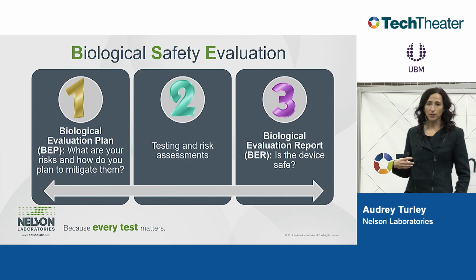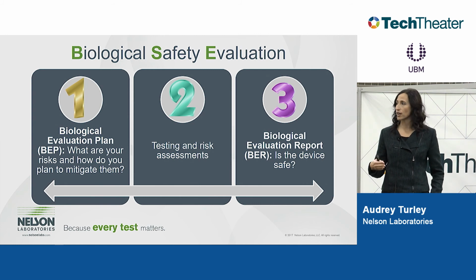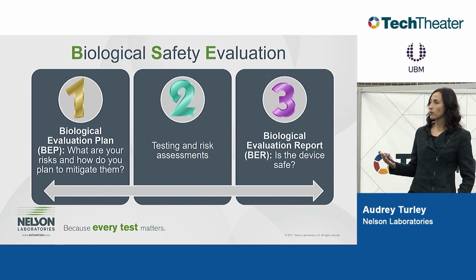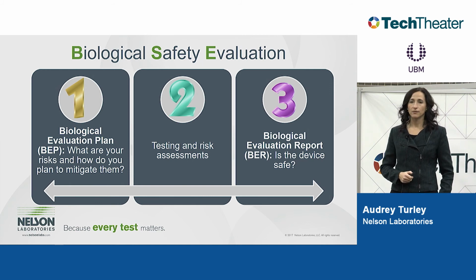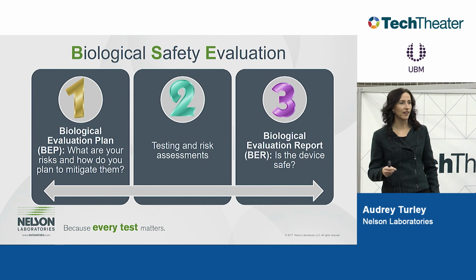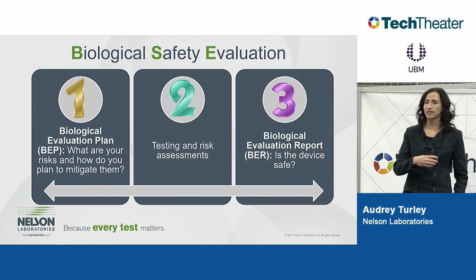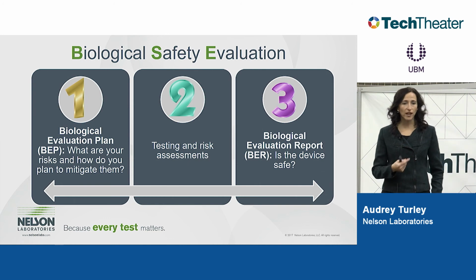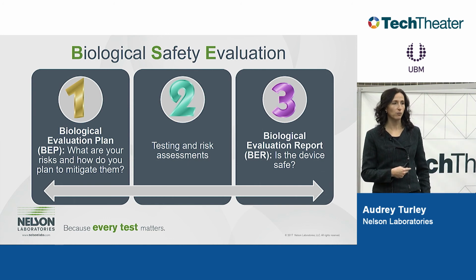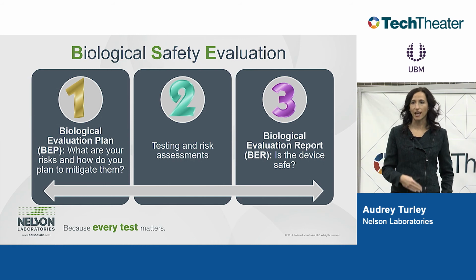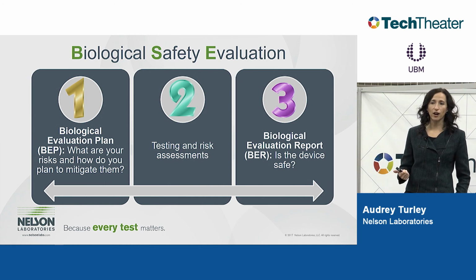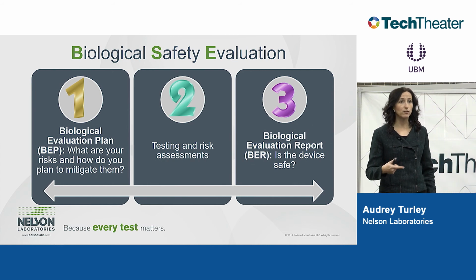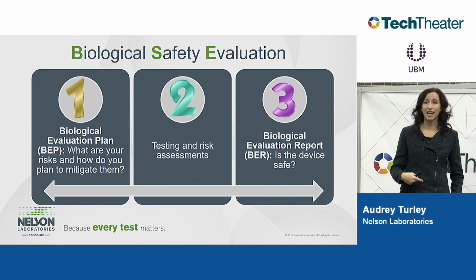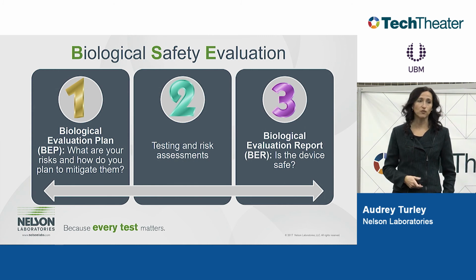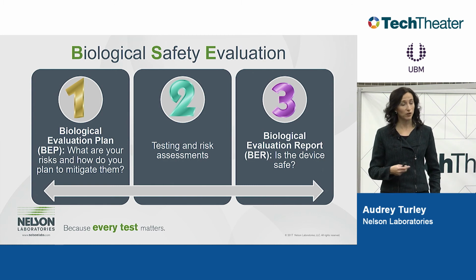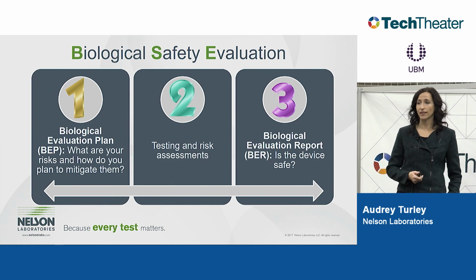So we step back out to this big picture. We've done step 1, we've done our testing, we've done our risk assessments, our chemistry testing, and now we're going to do a biological evaluation report. This sometimes gets a little bit of oversight, I think, and the engineer who was in charge of coordinating all the testing is just going to write everything up. But what we're finding is that agencies are coming back and saying we need somebody with the proper education and experience to say your device is safe. So they want somebody with some biocompatibility background, a toxicologist if necessary. Maybe you didn't do a separate toxicological risk assessment, but you need to have that input. You need to have that expertise reviewing these reports, or you will get kickback. We've had it the most from DEKRA, honestly, that they are looking for this.